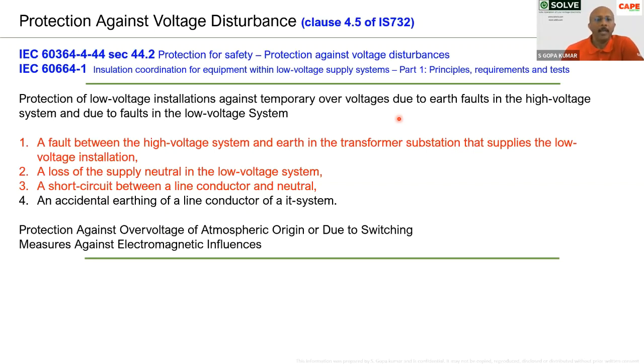Overvoltages are any voltage which is higher than these levels, for example, more than 230 or more than 400. Of course, up to 10% or in some countries up to 15% plus is allowed as a normal case. Say, for example, in India, 230 plus 10% means up to 253 volt between line to neutral or line to earth is the maximum voltage. Line to line, it can go up to 440 volt, for example.